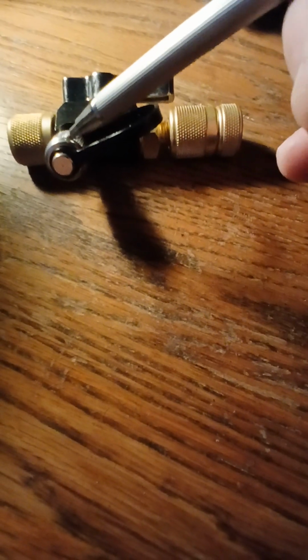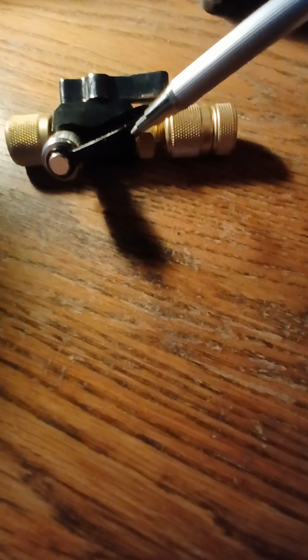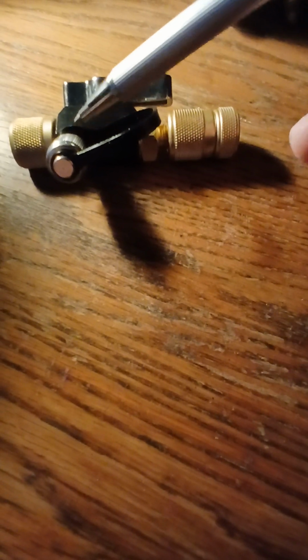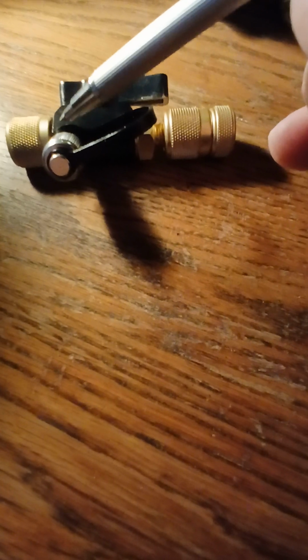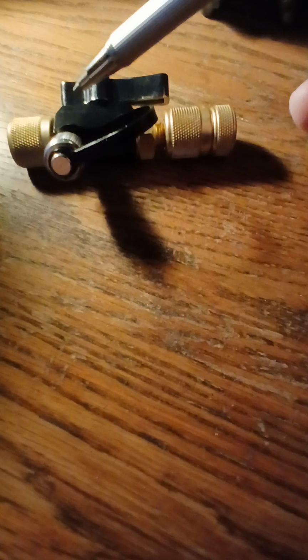But then let's just take this valve and hypothetically say it were in the back. Well, when this is cut off, then you have no way to technically check the pressure or whatnot. So perhaps this may be the reason whoever designed it put it towards the front, which to me is just a very genius idea. But anyway, the location of the charging or vacuum port, or the port to determine the PSIG of the system, if it's connected onto this side port here.